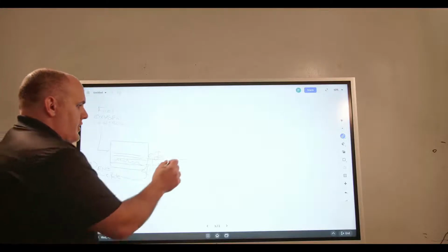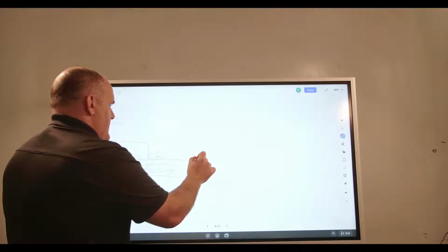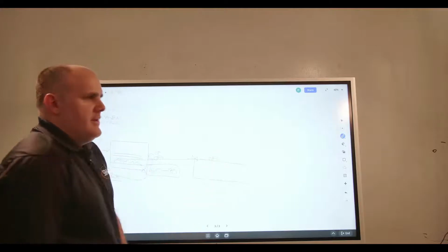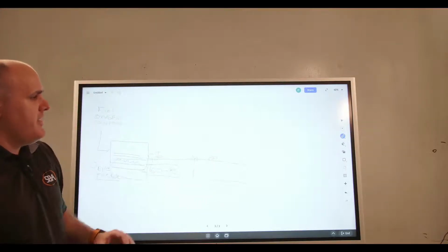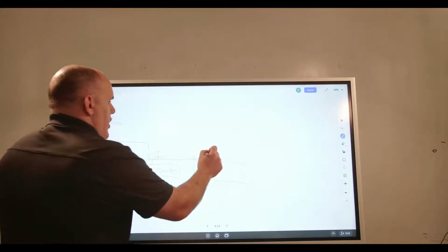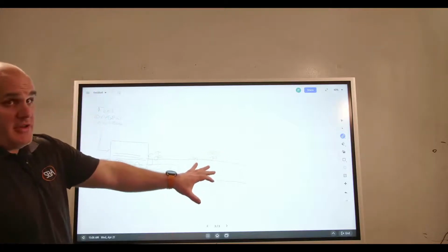So then going a little bit further on this, what we have going on is we have a mixing valve, right? We have a mixing valve here and a secondary loop. Just like with the chilled water plants, we have our secondary loop, and our secondary loop will typically have a VSD on this pump, and this VSD will enable us to vary the speed on the pump.